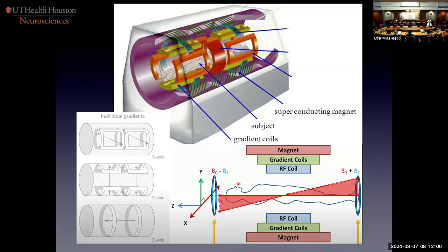When we send in the radio frequency, we're not going to blast your entire body — we wouldn't know where the signal came from when it comes out. So we first turn on a slice select and choose a narrow range of frequencies. For instance, if you wanted to image just your brain. Now look at the arrangement of the coils: I could turn on the X-axis and make sagittal images, turn on the Y and create coronal images, or turn on any combination of coils at the same time and get any possible imaging plane.